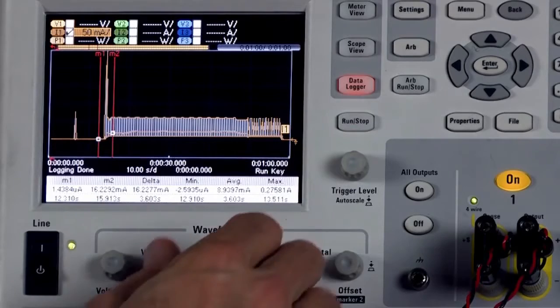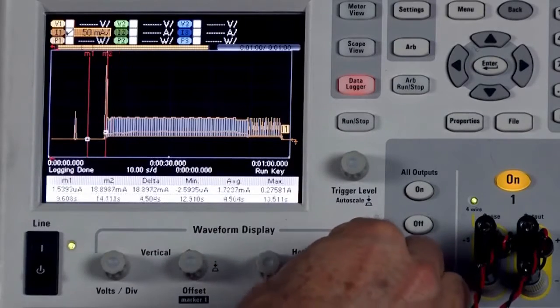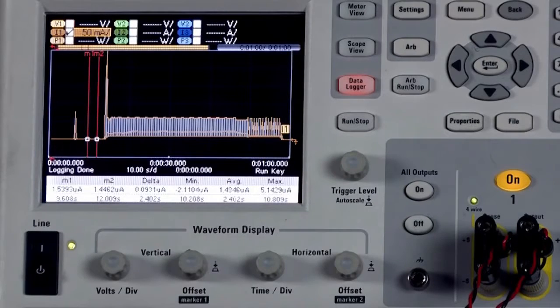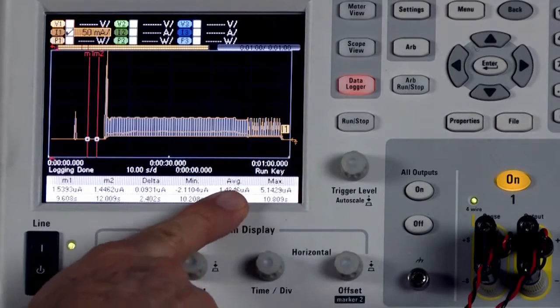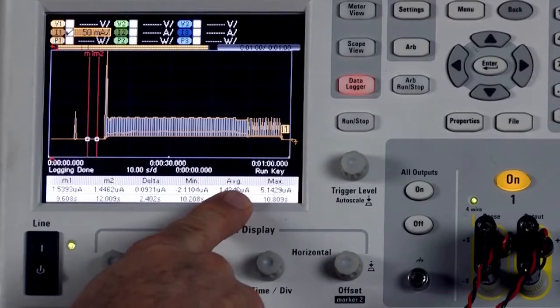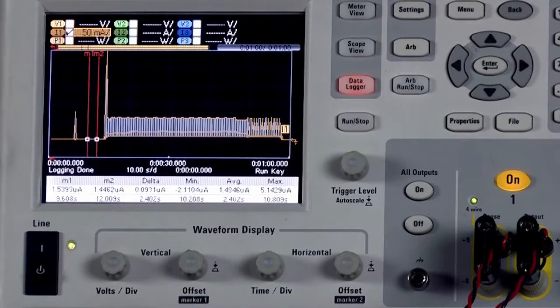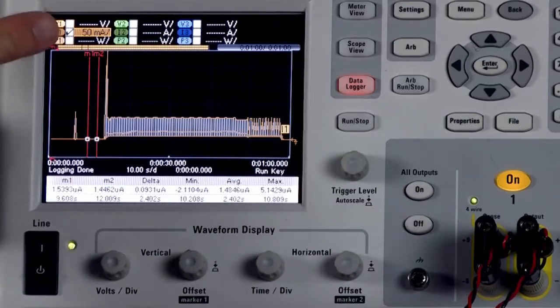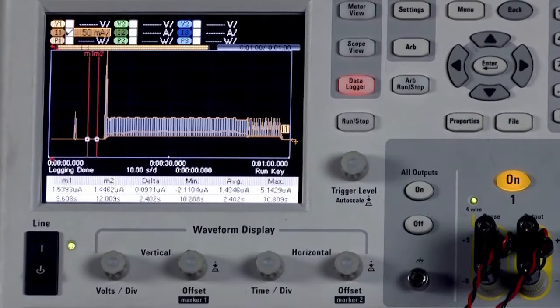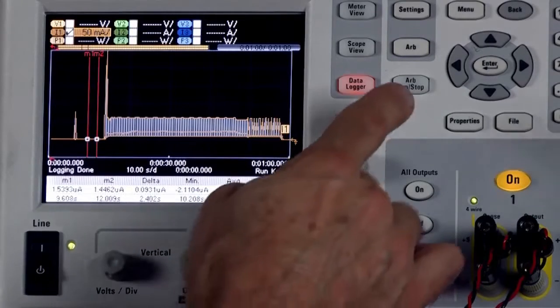So now let's move these markers and see what was happening down at the sleep current. So we had 3 volts power applied to the pulse oximeter, but it wasn't turned on. So they're trying to minimize the amount of current here. If we look at the average of this current, it's just 1.4 microamps, so very low drain on the battery. What I want to show is how well and how accurately we can measure that level. So I'm going to change our vertical resolution by 4 orders of magnitude, and we'll take a look at what kind of noise we have down at that 1 microamp measurement that I just mentioned.